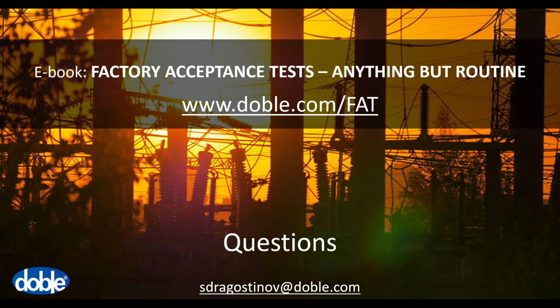No, I definitely would not recommend you pause the measurement and continue again. In case there are some issues noted during the measurement, either a high background noise level or some PD activity which is not coming from the transformer, or even if it is the transformer and the manufacturer decides to interrupt the test even for a short period, I would clearly recommend you start from the beginning.